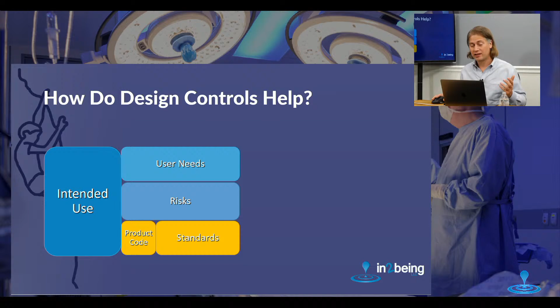Now, if you simply set out and said, let's go design something, and you didn't consider the needs of the user, the risks and mitigations associated with the device, and the standards that you need to follow, how would you ever design a device that was going to meet the inputs? You simply can't do it. So in this sense, not belaboring these points, but at least addressing them allows you to know what your device has to do. If you don't have it and you're just doing it by the seat of your pants, there's almost no way that you will design a device that meets what you're trying to do.